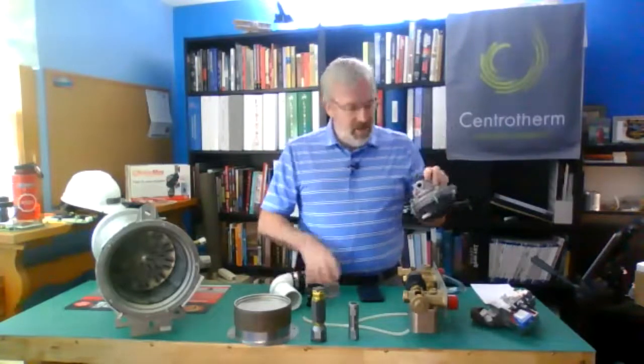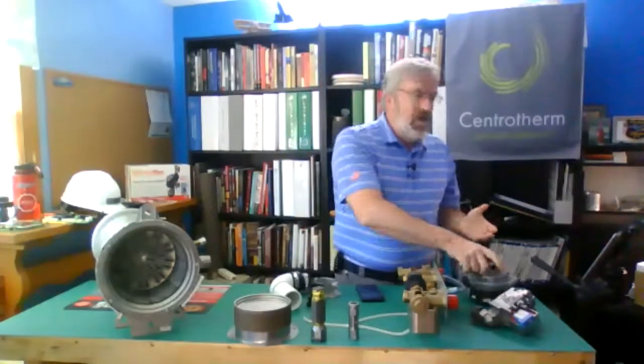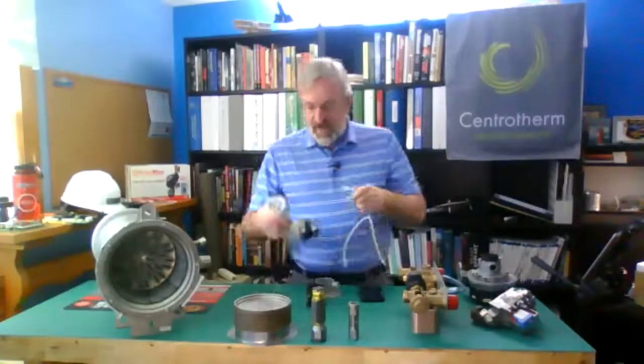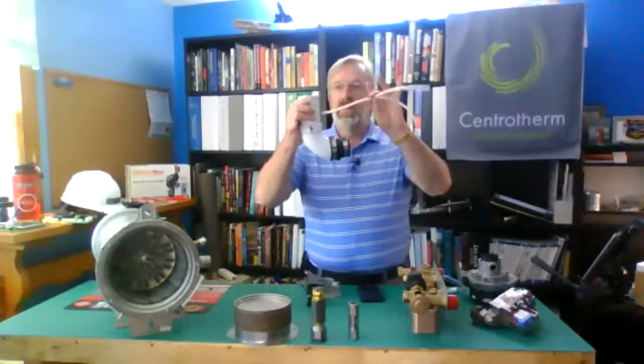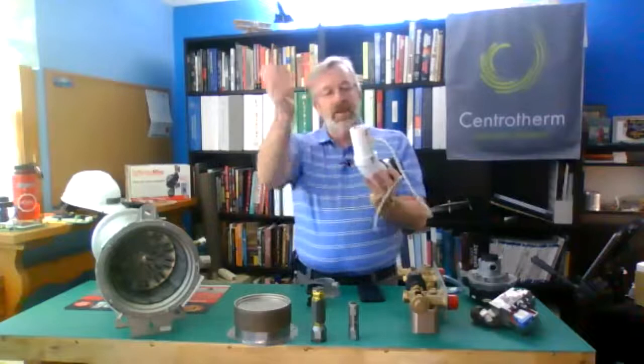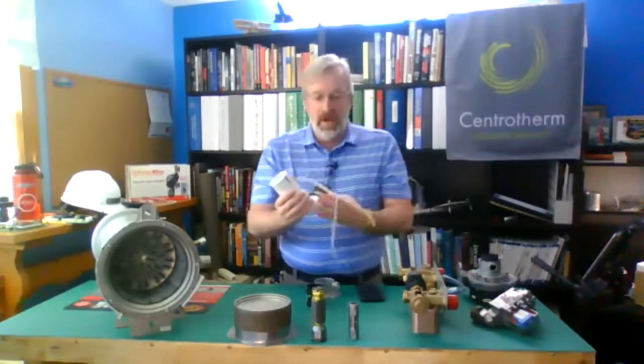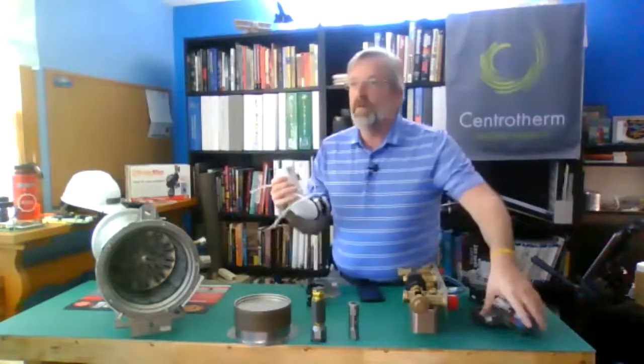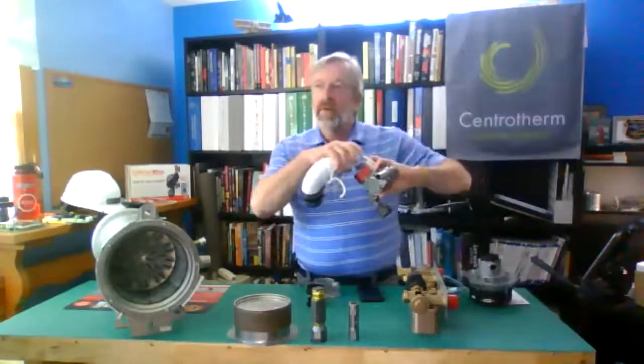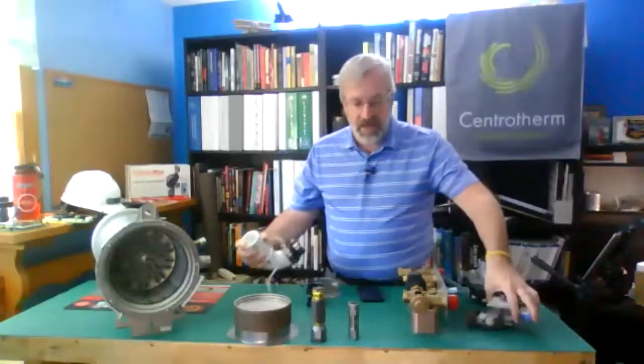So we'll step back to that PowerPoint presentation we had there for a moment. And we're going to talk about that negative regulation gas valve. So my fan, pulling my air through my venturi, drawing my gas in. So right now we're looking at the third leg of the stool, and that's the air side of everything. Now, before I get too far ahead of myself, one of the things that we do have in here is we got this reference hose on there, and that's actually referencing the true amount of air that's coming through here. One side goes to my pressure switch, and the other side goes onto my gas valve. And that's referencing the actual air.